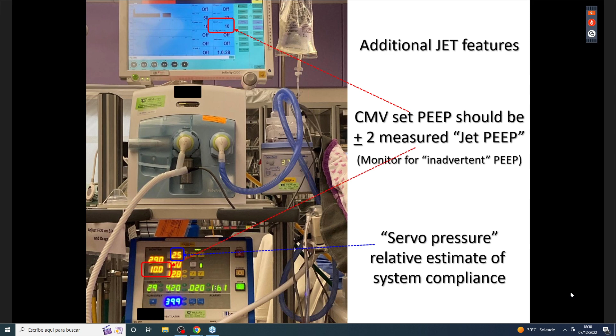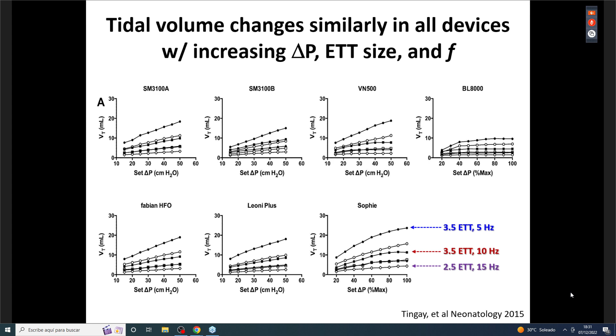I'm not going to go too much into ventilation. Everybody understands that tidal volume is a key component of how high frequency works. And importantly, with all high frequency ventilators, there is a marked diminution of tidal volume and pressure delivered as the gas moves down the airway. Bigger ET tubes have less resistance to flow, and therefore larger tidal volumes can be delivered with larger ET tubes.